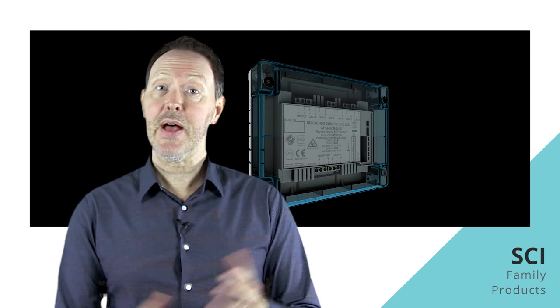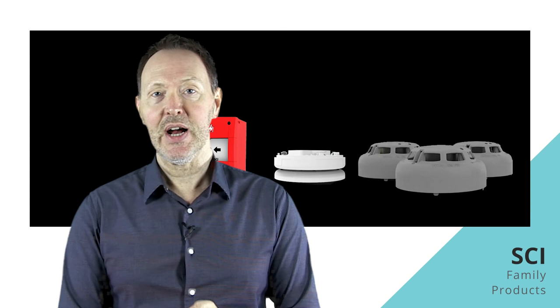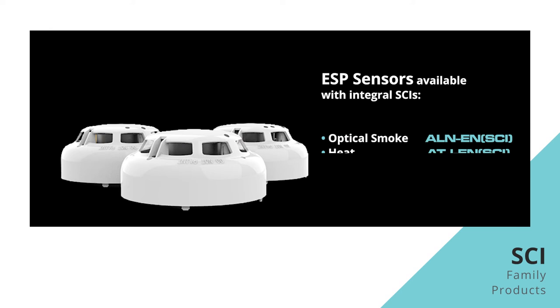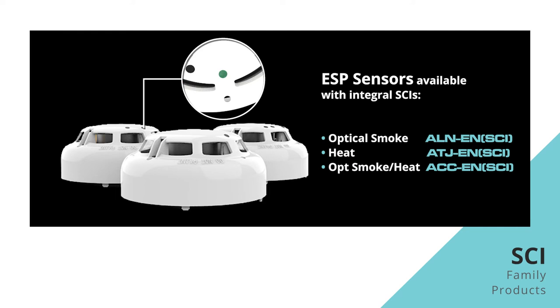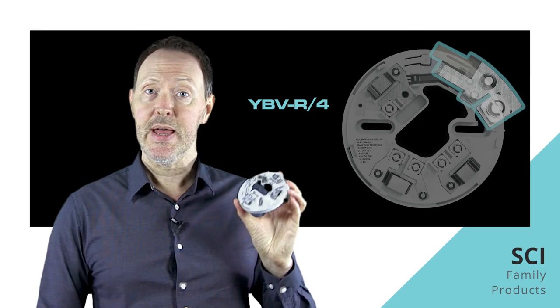Each of our standard addressable ESP sensors are also available as versions with integral SCIs. There's an optical smoke, a heat, and a smoke heat multi. The LEDs on these devices are tri-colored: green when polling, red when in alarm, and amber when the isolator is activated. Now to operate as SCI sensors, all three of these devices must be mounted on our YBV-R/4 mounting base. That's because this base has the additional terminal required to connect the SCIs within each device.